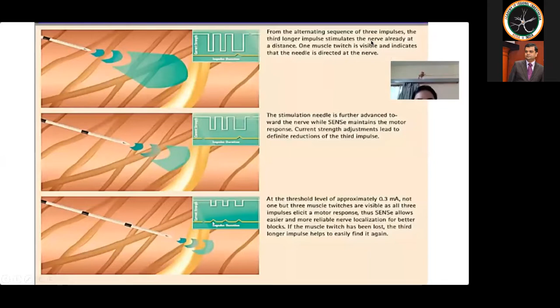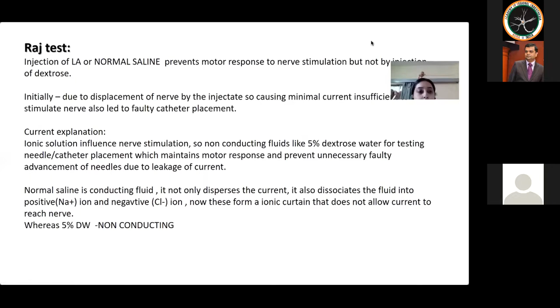Coming on to the Raj test, it is the injection of local anesthetic or normal saline, which will prevent the motor response, but not the injection of dextrose. This is mainly because normal saline is a conducting fluid, and it not only disperses the current, but it also dissociates the fluid into positively and negatively charged ions. So, this ionic curtain will not allow the current to flow through the nerve. So, we should use 5% dextrose, which is a non-conducting fluid.